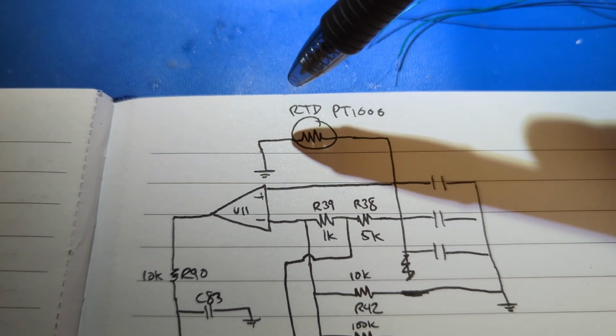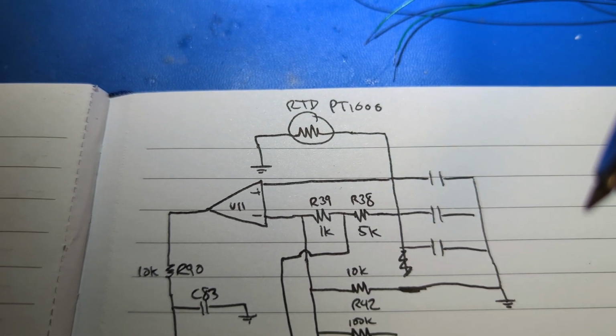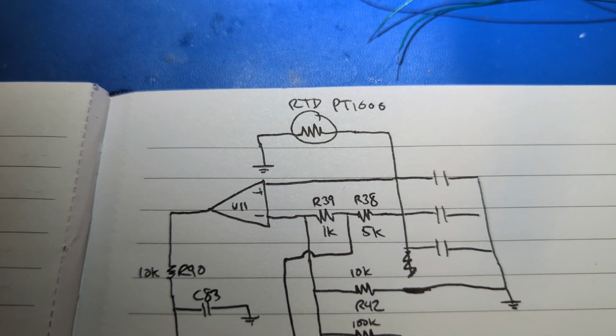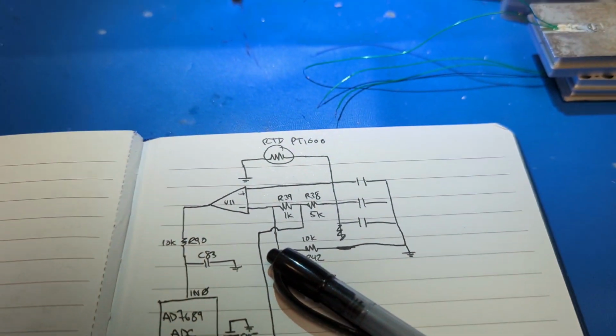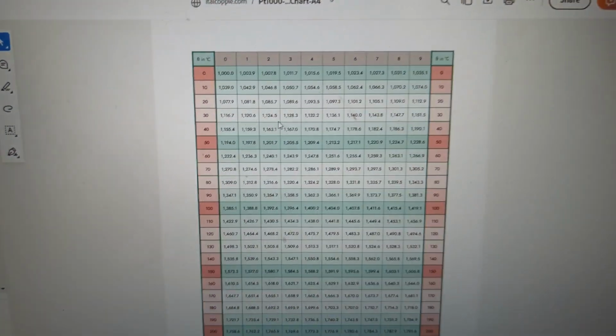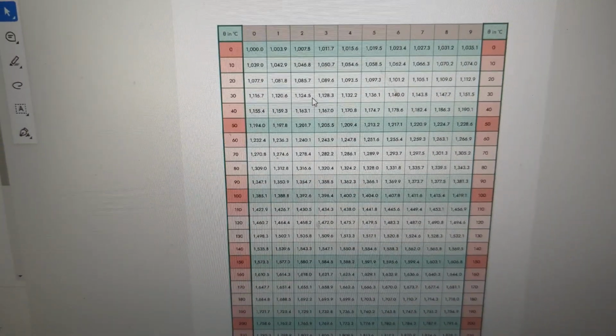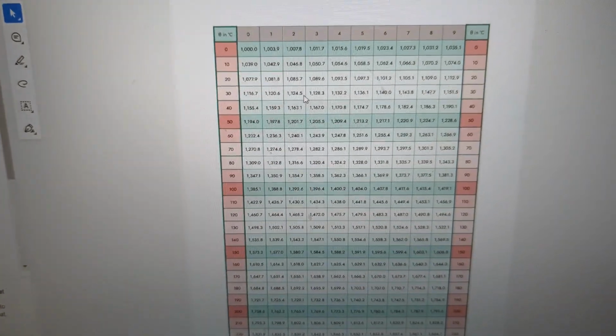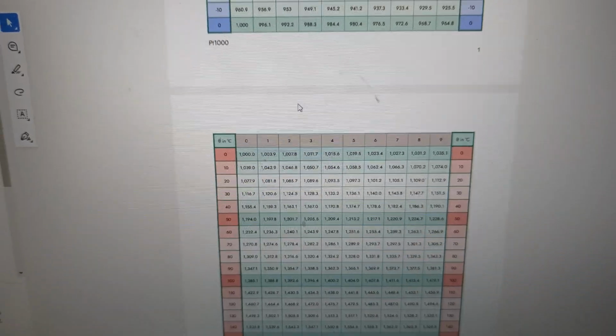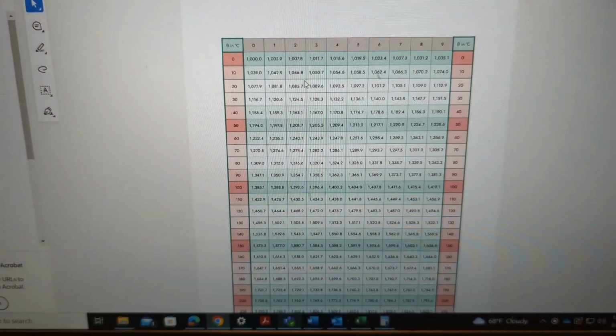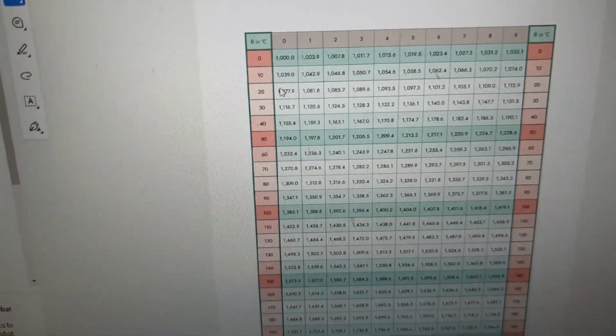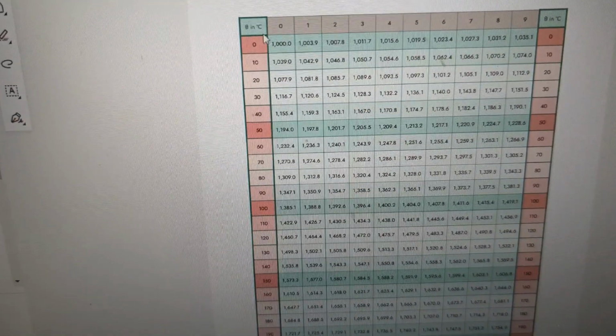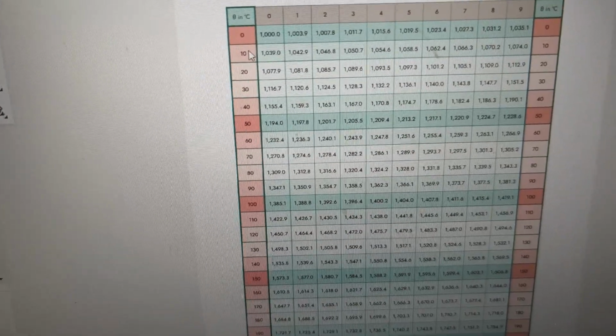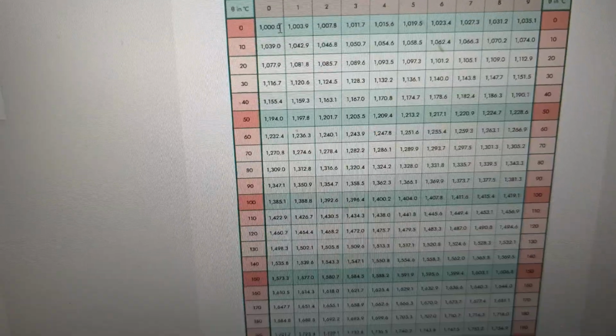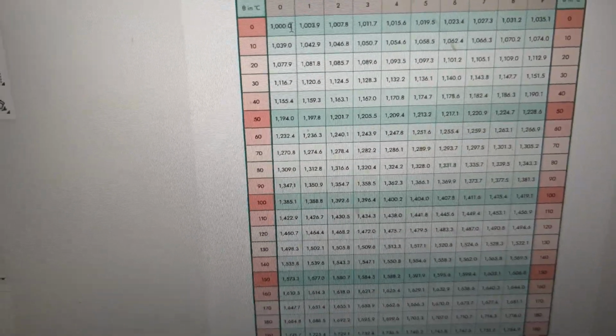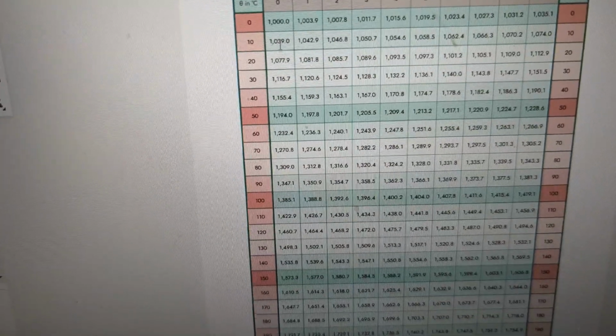If you were to look at an RTD temperature chart, for example, you would probably find that... let's pull one up and I can show you what I mean. Okay, so this is a chart comparing temperature and resistance for a PT1000 RTD, which is the exact same probe that these SimpliAmp PCR machines use. And this is what I'm talking about. Look, a jump from 0 to 10 degrees Celsius, that's a 10-degree jump, the RTD is going to respond to that by increasing resistance by 40 ohms.